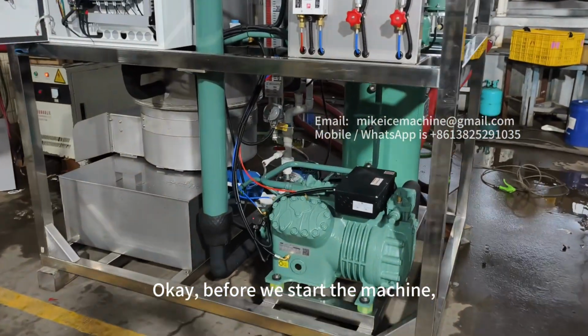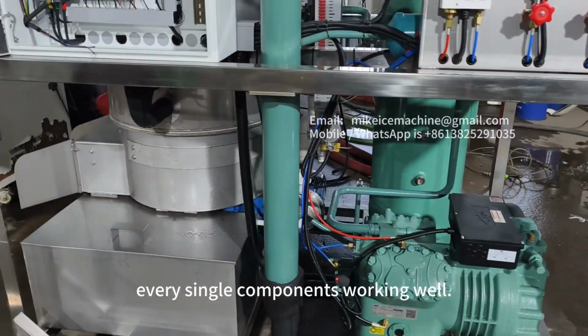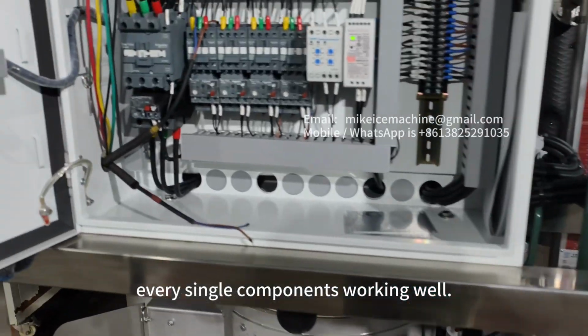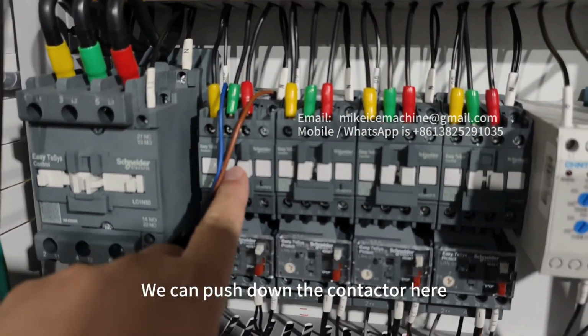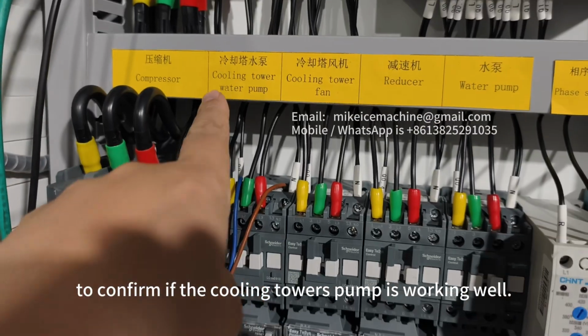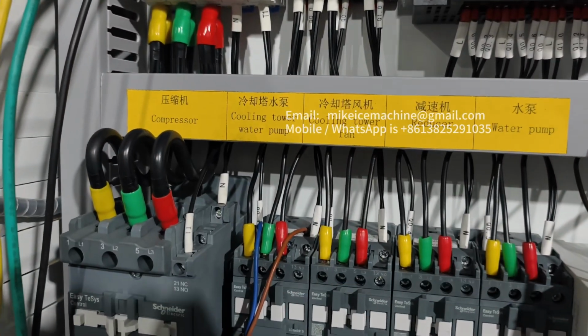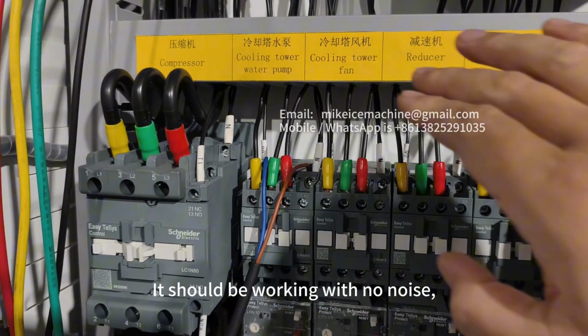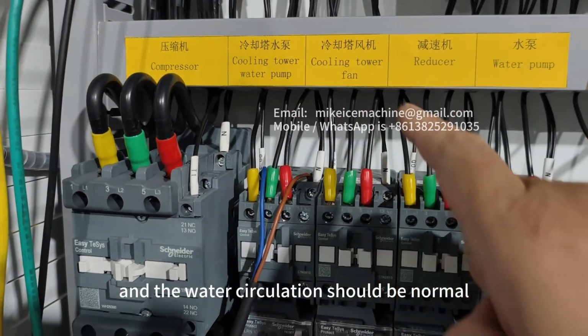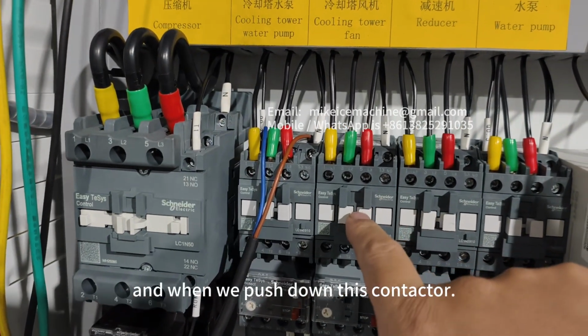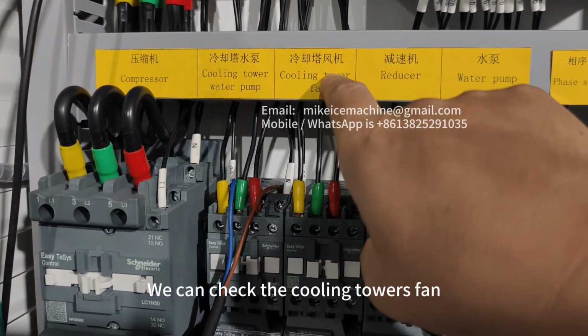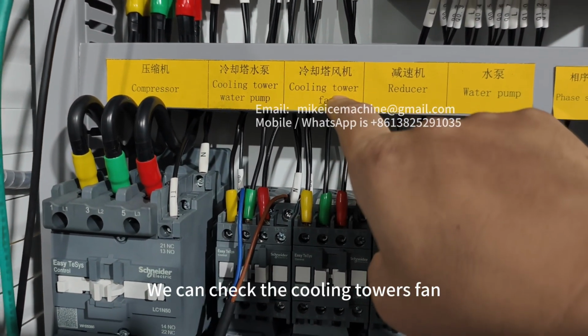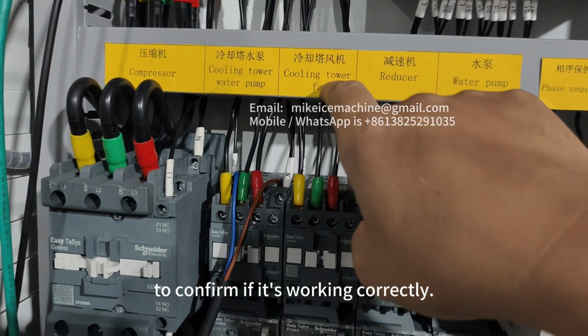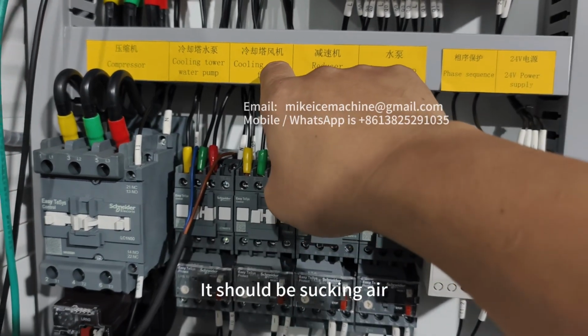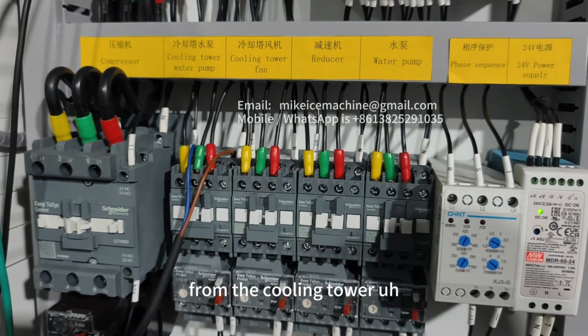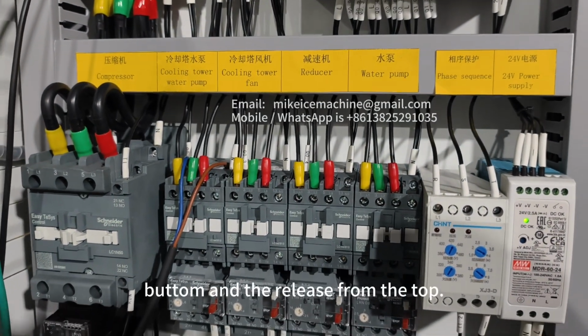Okay, before we start the machine, we need to make sure every single component is working well. We can push down the contactor here to confirm if the cooling tower's pump is working well. It should be working with no noise, and the water circulation should be normal. And when we push down this contactor, we can check the cooling tower's fan to confirm if it's working correctly. It should suck air in from the bottom of the cooling tower and release it from the top.